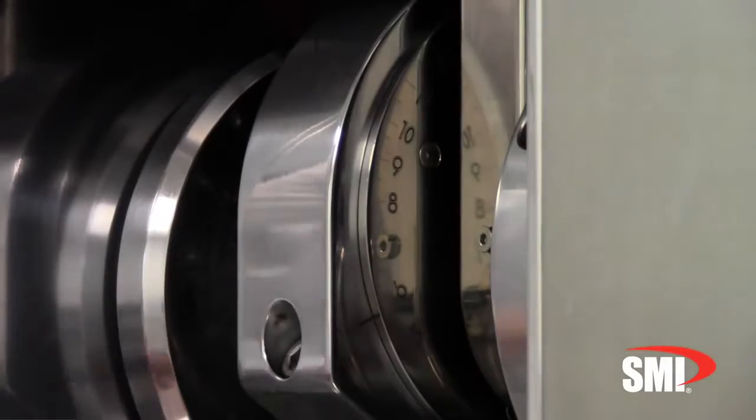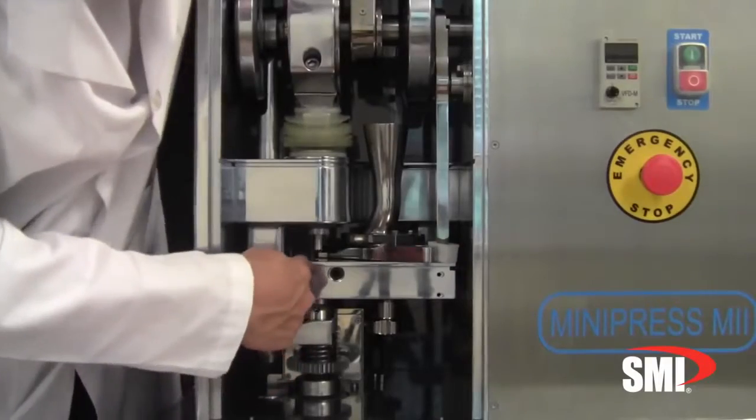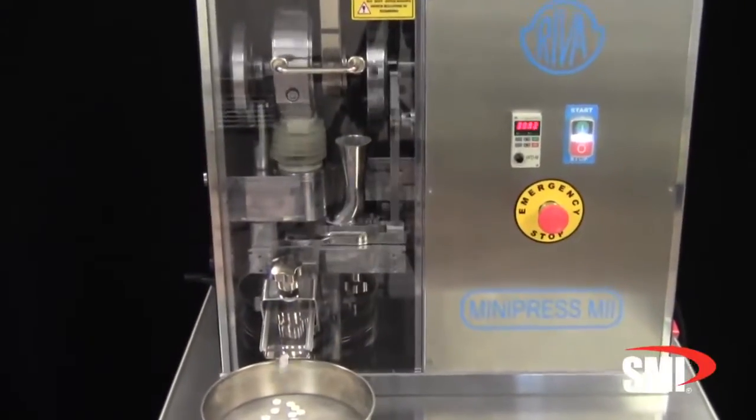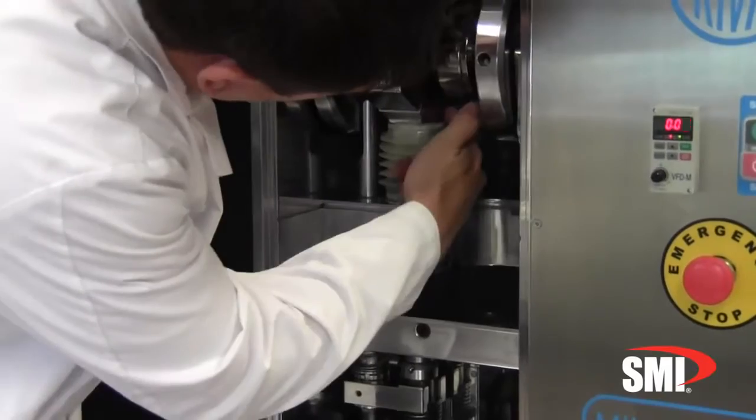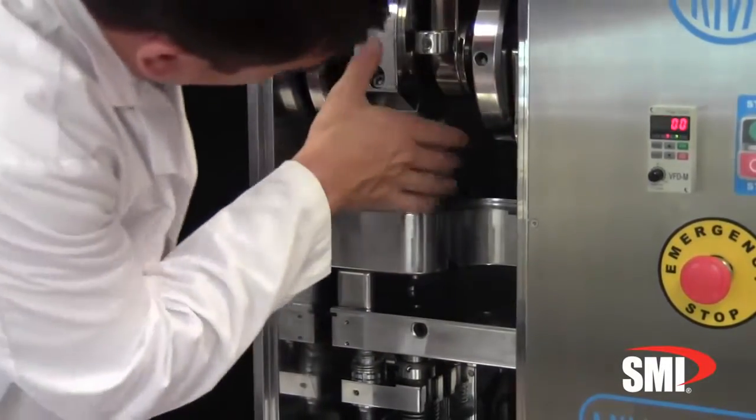Variable upper punch penetration for tablet thickness and compression force, adjustable ejection height, trolley integrated instrumentation allowing for quicker cleaning times. All 4 sensors are custom designed by SMI, allowing accurate and reliable data for all your tablet size requirements.